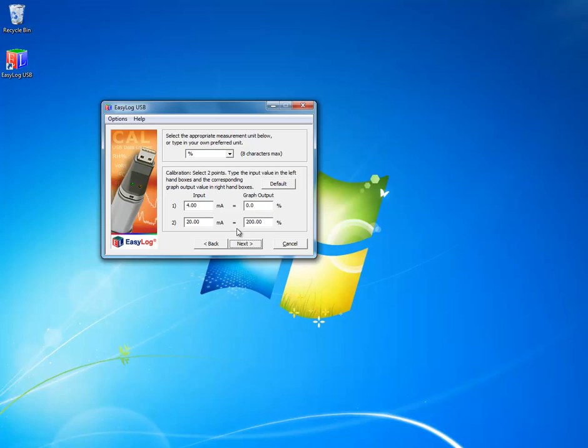The default value is a percentage, but we don't want a percentage. We want a flow rate such as SCFM or cubic meters per minute. So type in SCFM or if you're using one of our meters that has cubic meters per minute, type in M3 per minute.